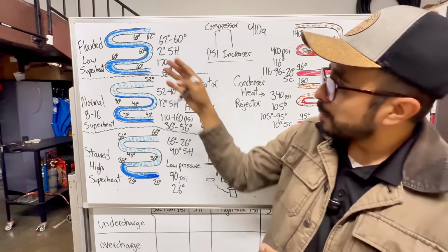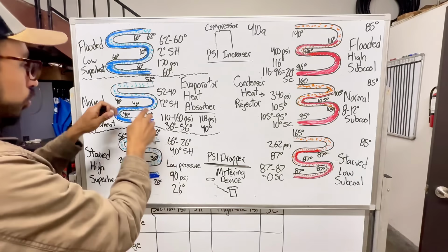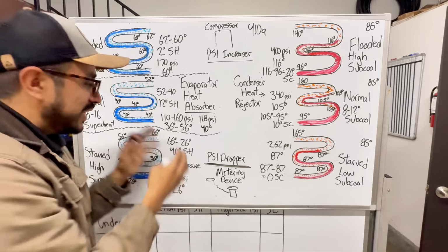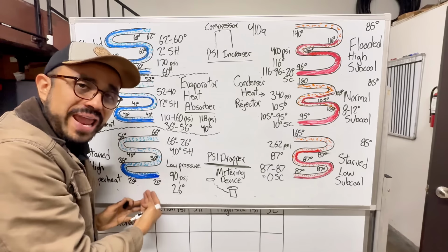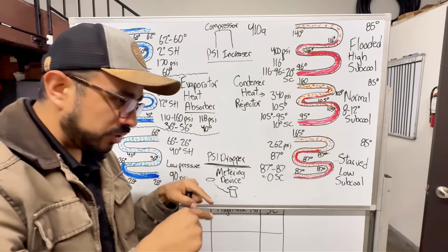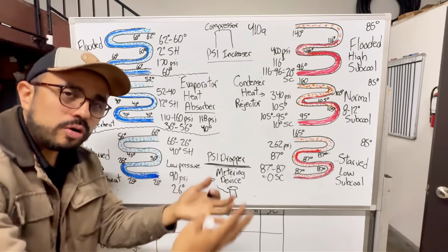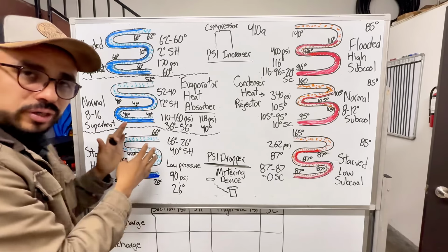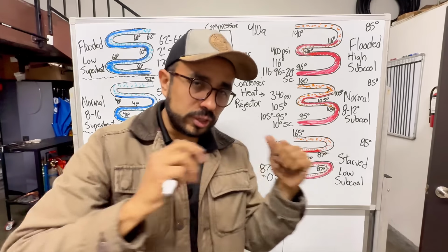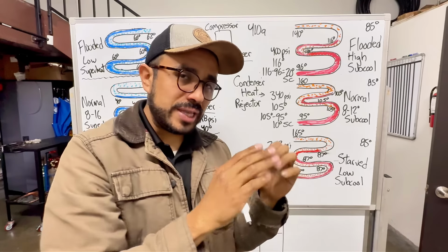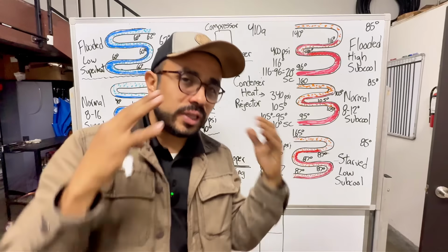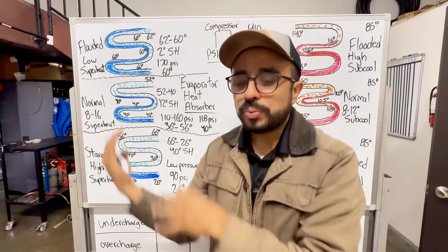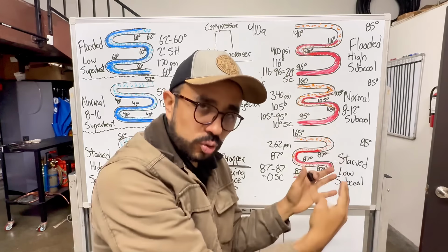Now for your evaporator, we know that the evaporator is cold. The key here is the return air temperature, where your filter is at. That needs to be warmer than your evaporator. So you see what I'm trying to get across with that point: there has to be a temperature difference so you get a good superheat number and a good subcool number.